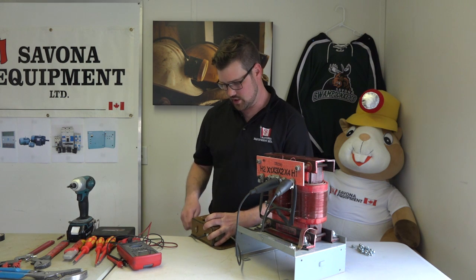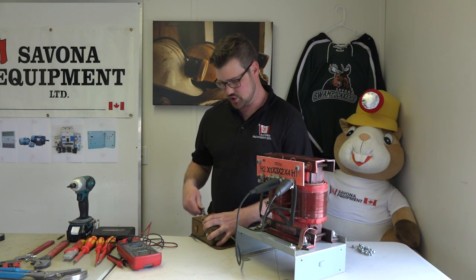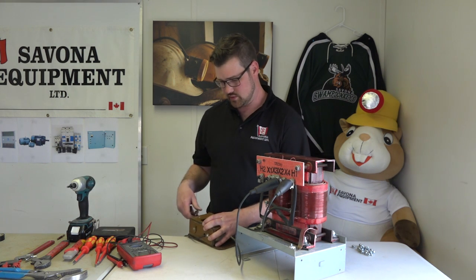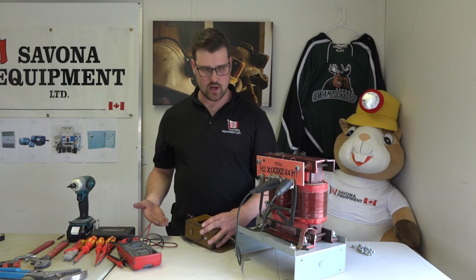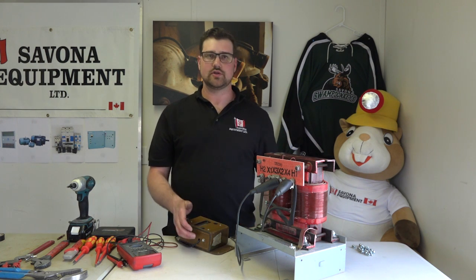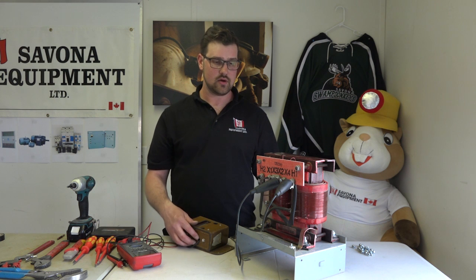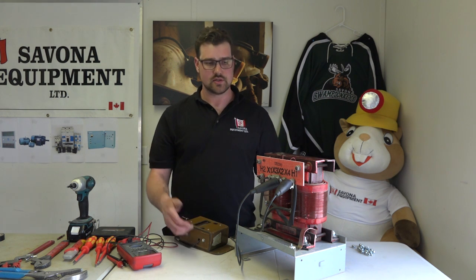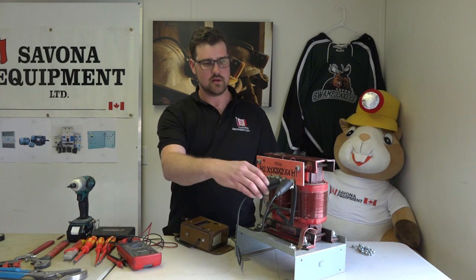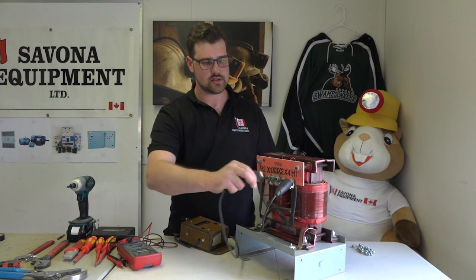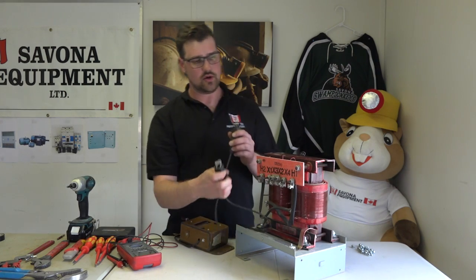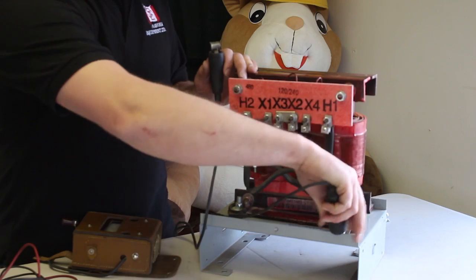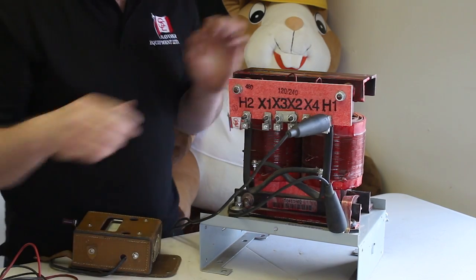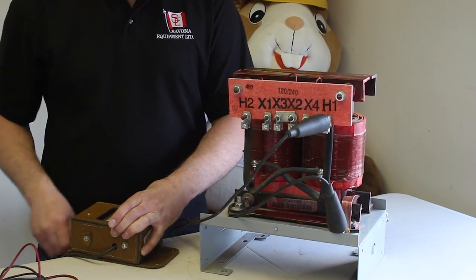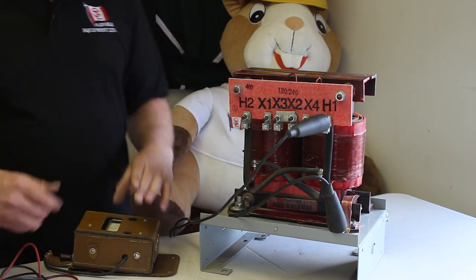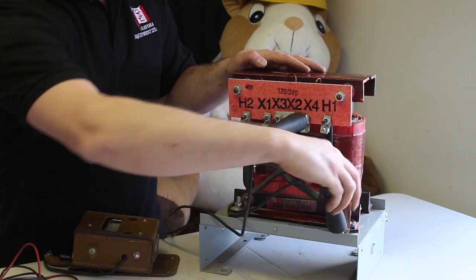So I'm just simply watching on the megger, making sure that it's increasing, and it is, so that's a good sign. And then I'll let it wind down a bit here. You can also use a digital megger that has a ground connection, so that you don't have to wait for this to dissipate, but there is a little bit of energy that will be stored in this. So next I'm going to do the high voltage to ground. Yeah, that's good there. And then I'll do low voltage to ground.